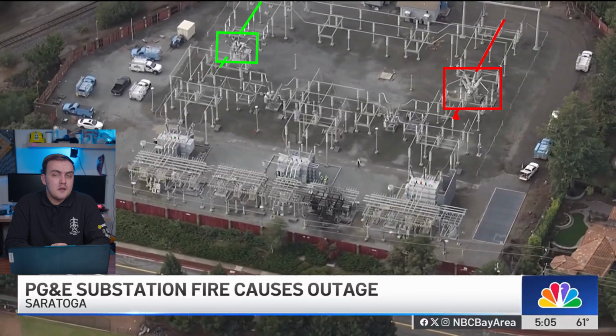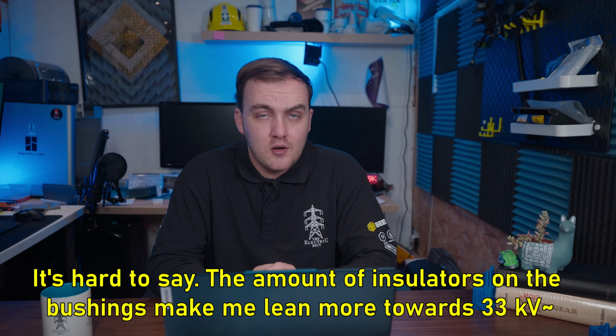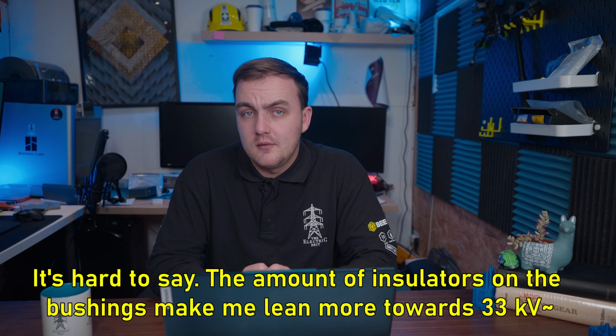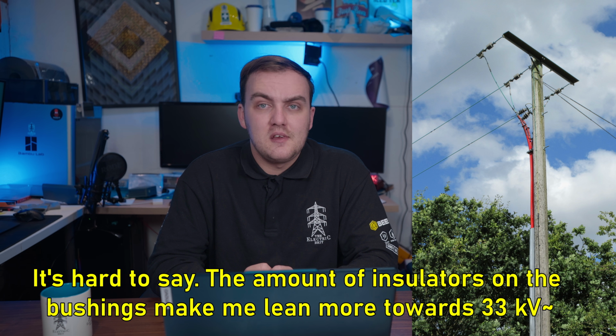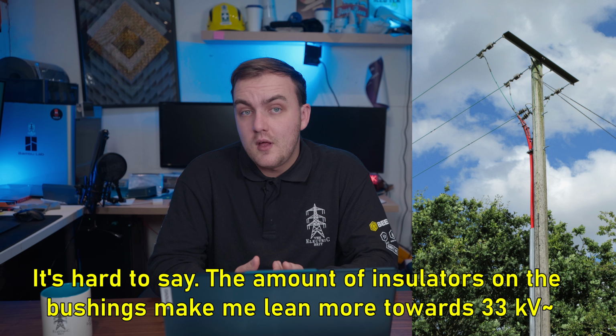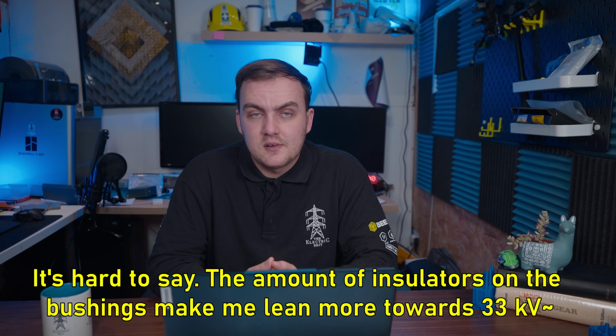As we come down, we get to this T-junction on the bus bars, where it goes up at an angle and over to the transformers here, which as mentioned is taking the high voltage 230 kV at the upper side, where the bushings are higher and spaced out, to the bottom side here, where they're much smaller and closer together, so we know this is the lower voltage side. Distribution voltages vary in the US, but this looks like 12 kV judging by how close these bars are, and in the UK we use 11 kV, which is the stuff up on wooden poles you see near homes, but this could also be 33 kV, but information on this site is sparse.